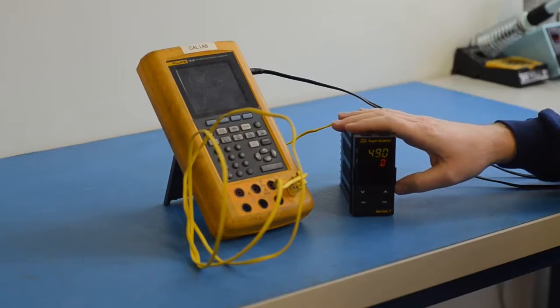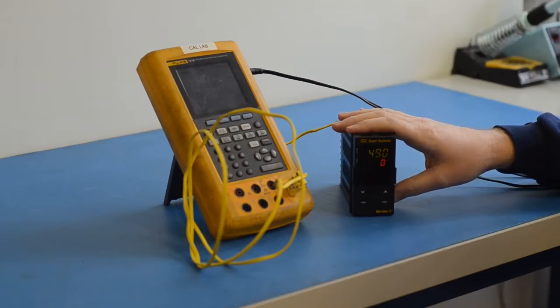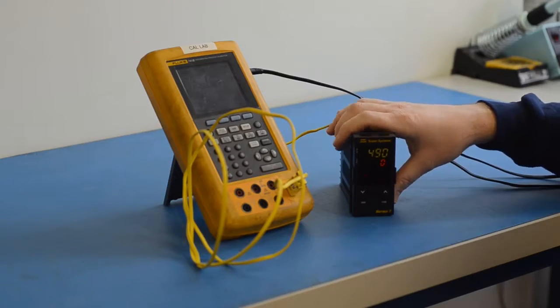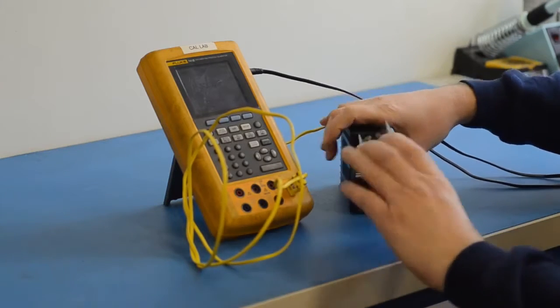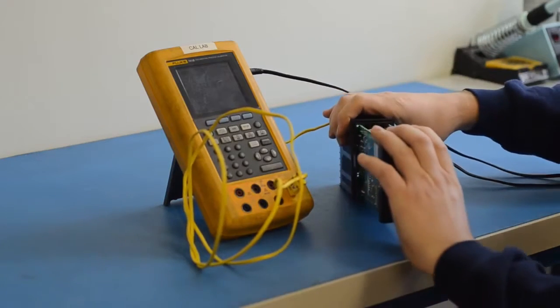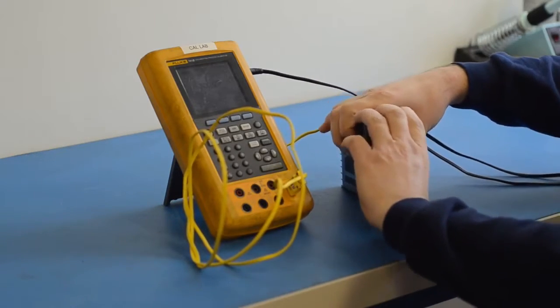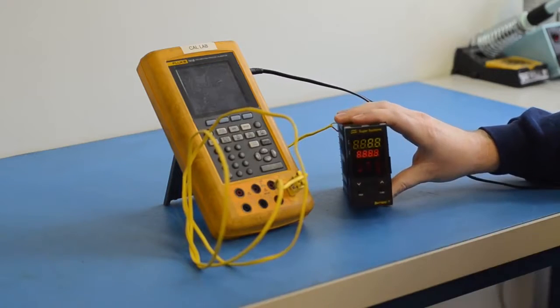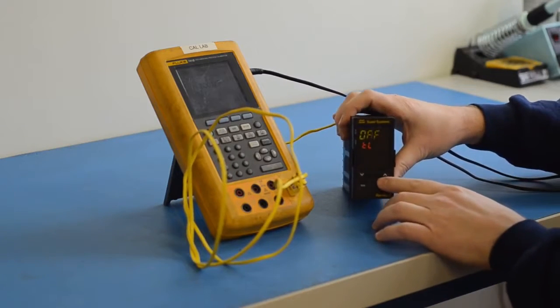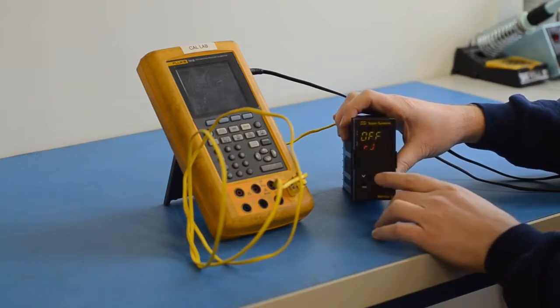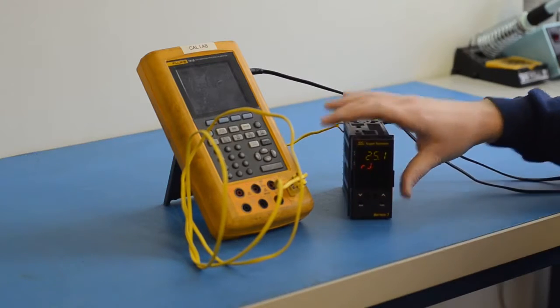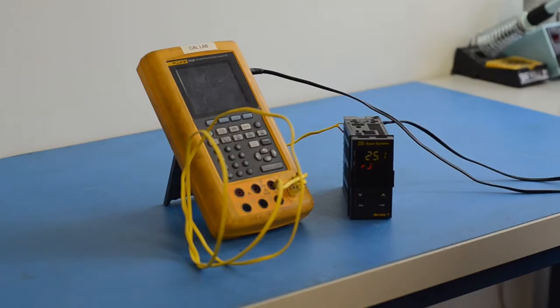So now we're reading a lower temperature, and if you go too far, you will have to then repeat the steps of removing it from the case, unlatching the jumper, reinsert it into the case, and adjust our RJ value again until we get it within plus or minus 1 degree of the value that we are sourcing in from our gauge.